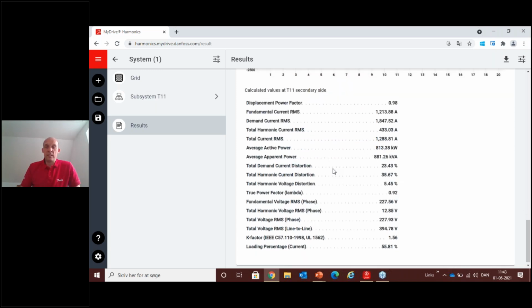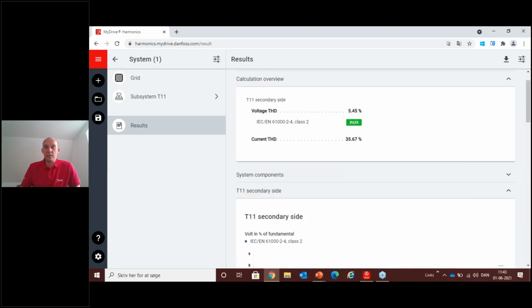So the result here tells me I have a 5% voltage distortion on my power supply. It's higher than 5%, but very close to 5%. And I have a current distortion of 35%. For this specific example, I would not do any mitigation, because you are so close to 5% that it's probably not going to give you any issues at all. You have very good power quality in this example.